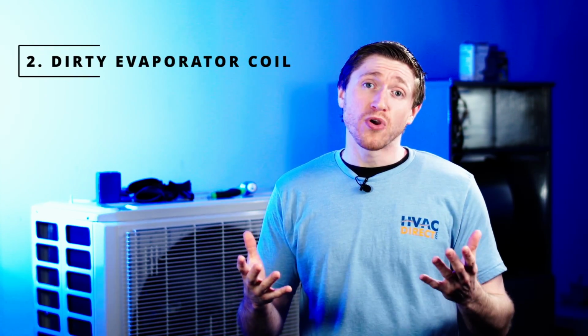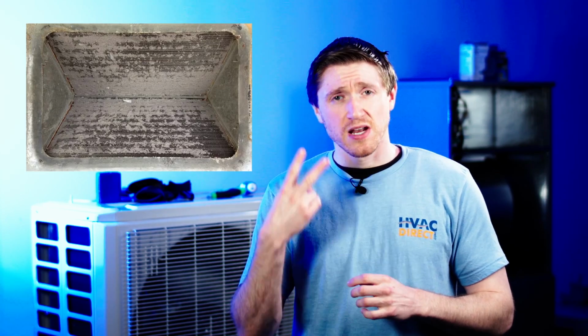Option number 2, which is a little bit harder to fix, but still not too bad, is you have a dirty evaporator coil. If the evaporator coil gets dirty, that can interrupt the condensation from flowing properly down the evaporator coil. At that point, what you're going to need to do is clean the evaporator coil. The reason I have this at number 2 is it's normally relatively easy to get to your evaporator coil, and it's not too hard of a task to clean. If you do struggle to get to the evaporator coil or you don't feel like you can clean it yourself, we would recommend having a service technician from your HVAC company do that cleaning for you. But the good news is once you get it cleaned, it should start draining properly. That was option number 2.